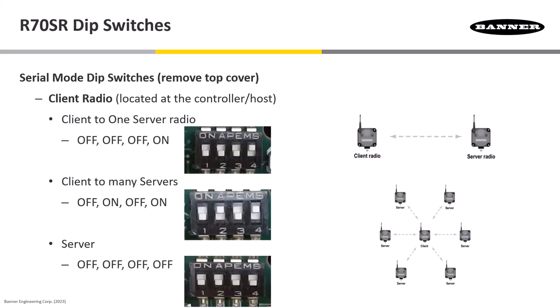In serial mode, looking at the DIP switch setup for the client radio, which is the one that would be located at the host or the controller, the only one that we're going to be turning on is the fourth DIP switch when we're talking from one client to one server. If we're talking to many servers or repeaters, we are going to turn on that second DIP switch there. So we'll be in an off-on, off-on setup for the client. And for the servers, we're going to have all four DIP switches off.